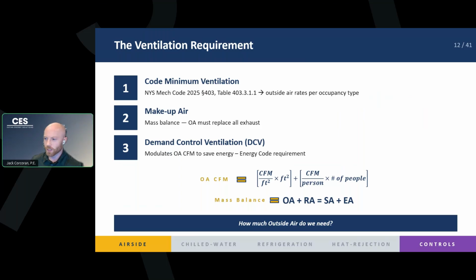That total, the equation at the bottom, you see there's 2. The top one is that equation, right? You get those rates of the CFM per square foot, your CFM per person. You calculate out based on how many square feet and people you have, and you get 1,000 CFM or 10,000 CFM, whatever it ends up being. That is your code minimum, and you have to bring it into the building. We're bringing it in per code, but really in reality, the driving forces are indoor air quality. You don't want stagnant, stale air, and different occupancy types might require more or less conditioning or fresh air to be brought into the space.